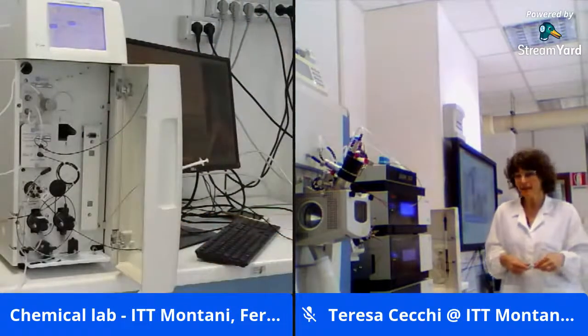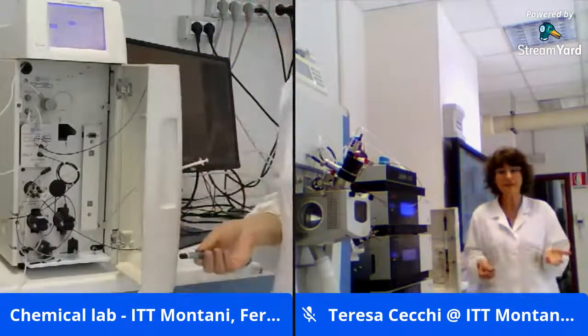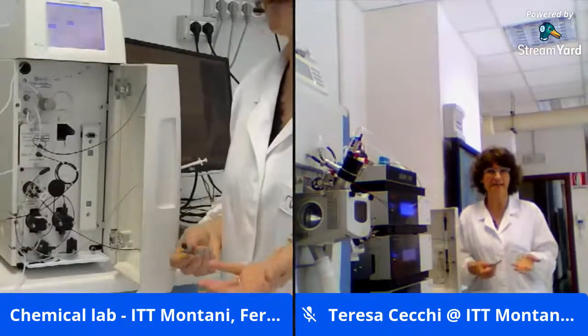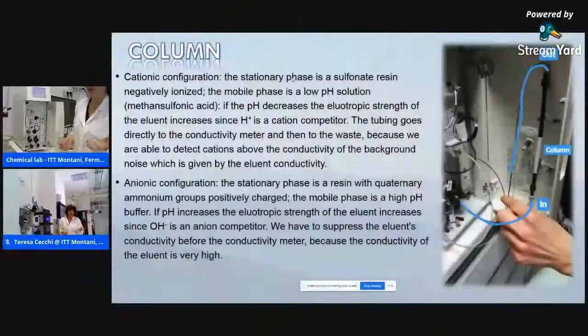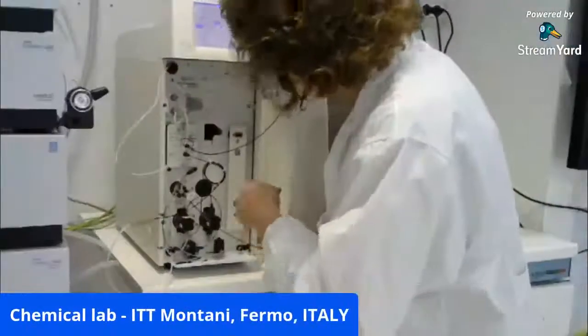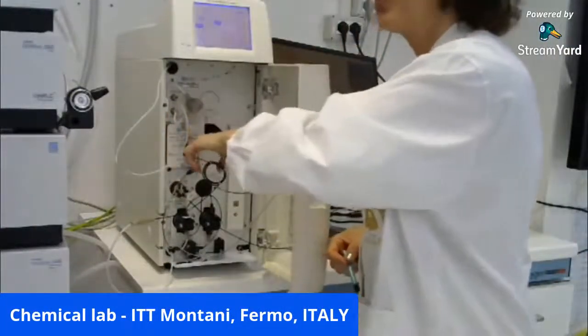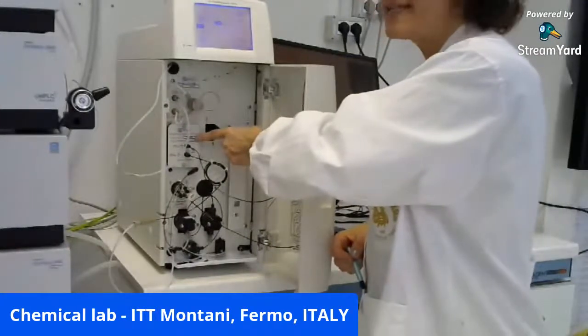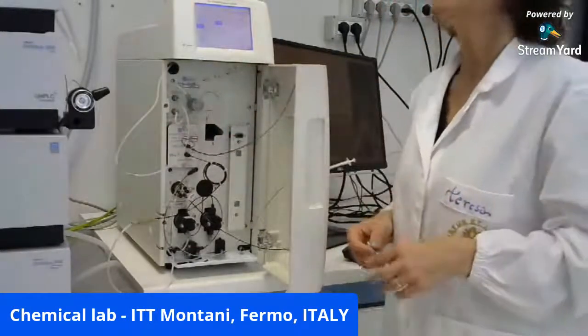Instead, in the anionic configuration that we use, for example, with acidic drugs, or also inorganic ions, think about fluoride in a toothpaste, for example, the stationary phase is a resin with positively charged quaternary ammonium groups, which interacts with acidic and negatively charged analytes. In this case, the column effluent from here could not directly go to the conductivity cell, which is the detector, but needs to be suppressed.